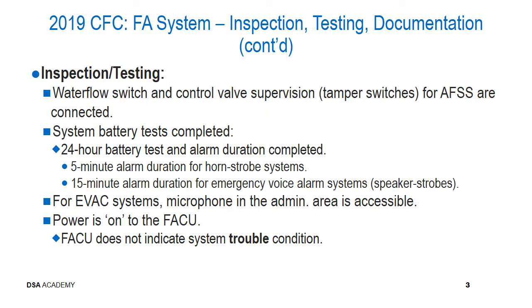As part of the inspection and testing of fire alarm systems, we're going to be testing those elements that are associated with the fire sprinkler system as related to the fire alarm system. So that includes water flow switches, control valve supervision switches, i.e. tamper switches, and that they are connected to the panel, and when operated, the appropriate supervisory signal is transmitted and reflected on the fire alarm control panel.